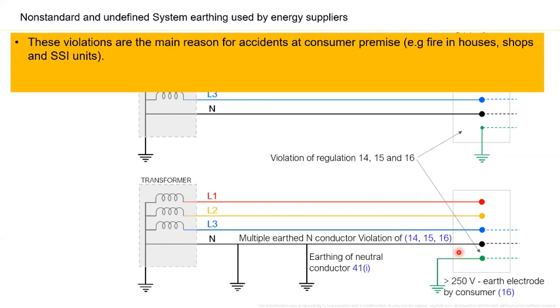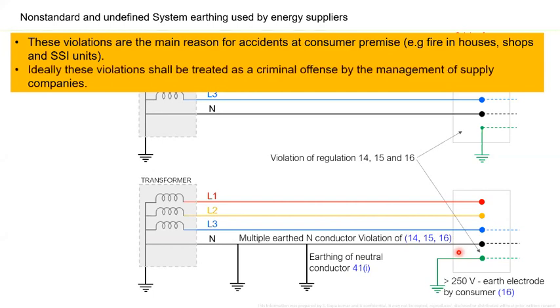Basically, there is a fault. You can imagine the consumer is having some kind of problem. There is a fault and the protective device is supposed to trip. It is the responsibility of the power supplier, the energy supplier, to ensure that the consumer premise is protected. Of course, the consumer also has certain responsibilities, but it doesn't mean that the responsibility is only with the consumer; the supplier also has a responsibility. And that is the purpose of making the regulations. All these regulations are violated. 14, 15, 16, very, very important.